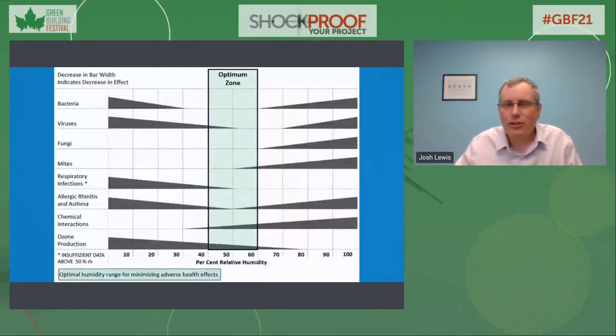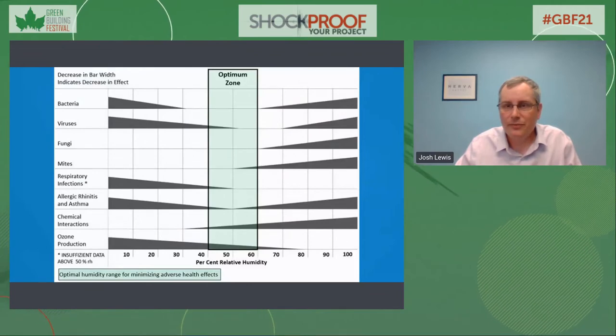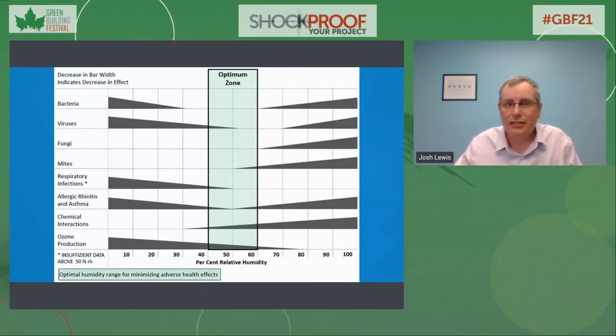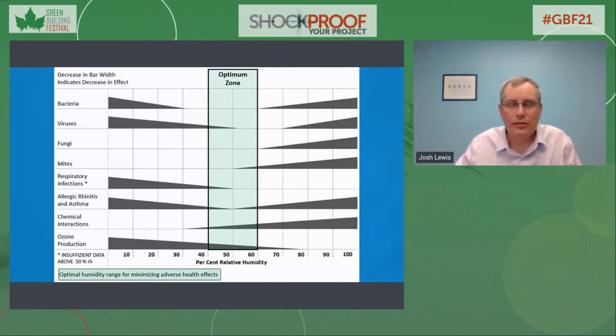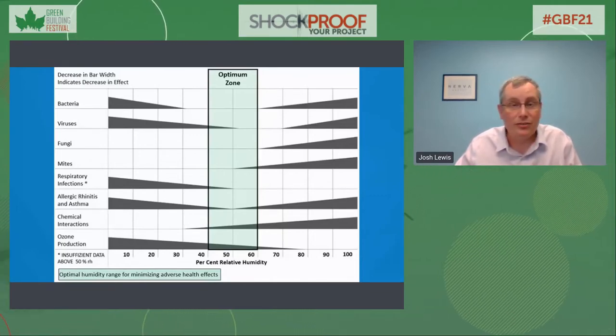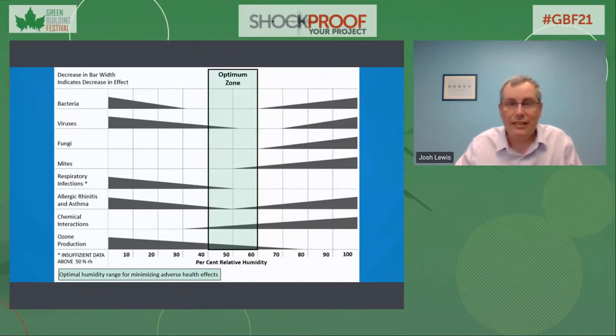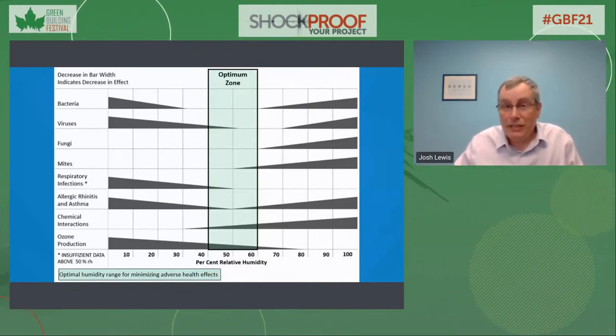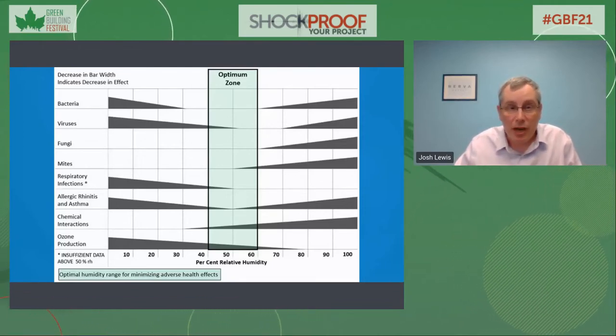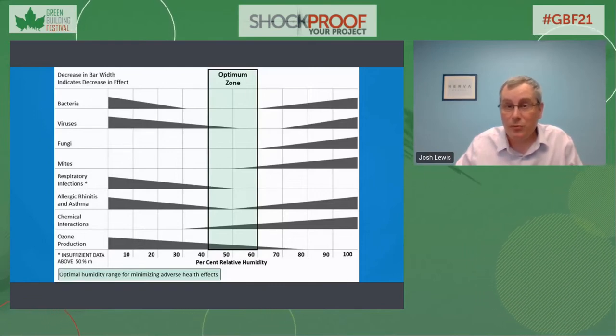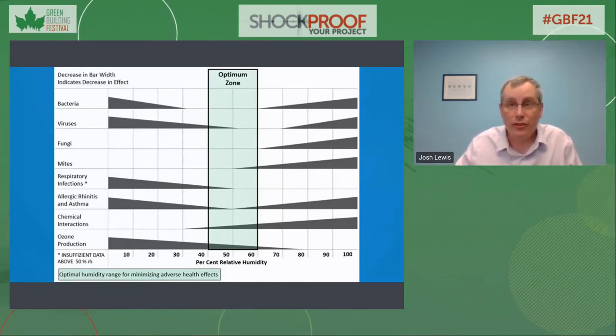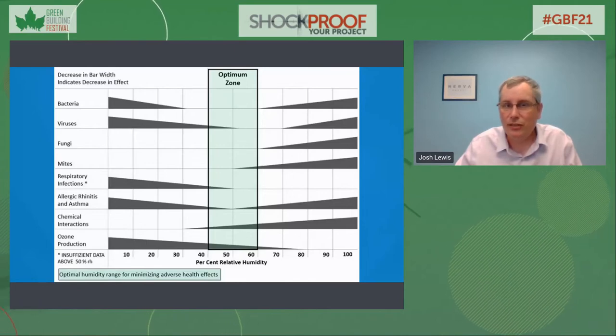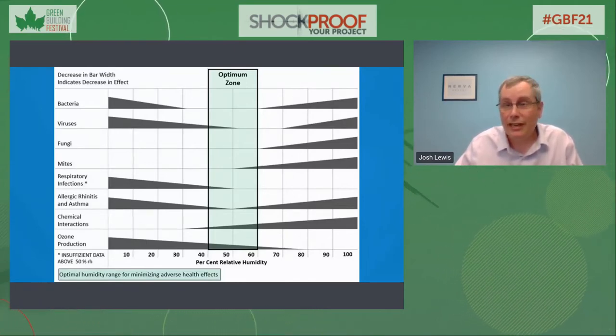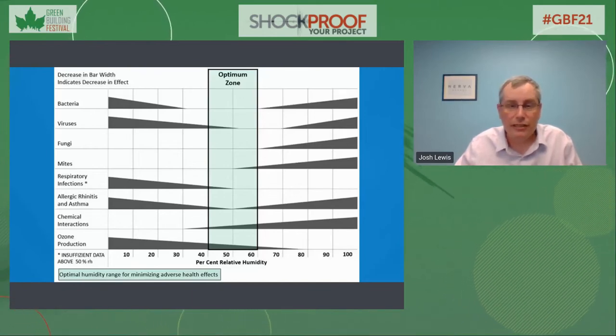The last key operational parameter for a healthy environment is humidity. As you can see on the graph, many years of research has clearly shown that the control of humidity levels in buildings is critical to maximizing indoor air quality. Whether talking about bacteria, viruses, fungi, mites, or other contaminants, they are all minimized if the relative humidity is between 40 and 60%. If possible, controlling to a tighter range of 40 to 50% indoor air humidity will also keep the mold growth at very low levels. Correlatively, keeping humidity under control has also been shown to have many other indirect benefits, including reduced absenteeism, improved occupant mood, and increased productivity, all of which are likely the result of people within the building being healthier.